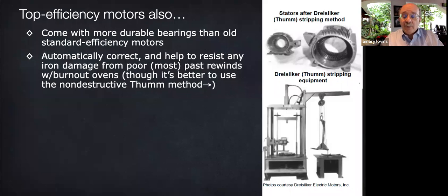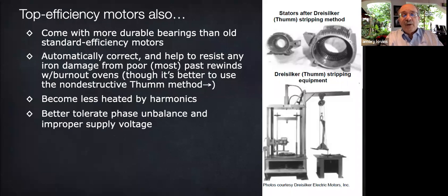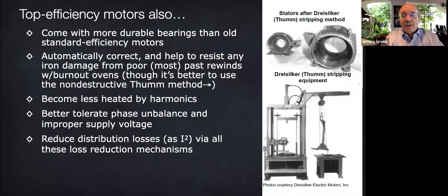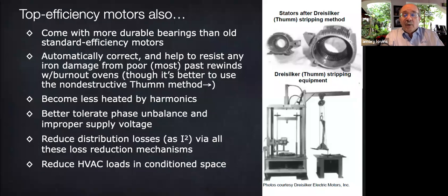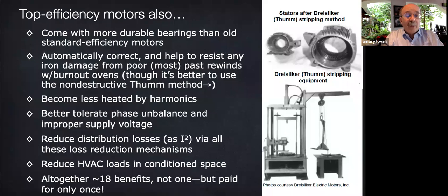Moreover, the top efficiency motors have less harmonic heating. They better handle phase unbalance and wrong supply voltages. They cut the I²R losses in the distribution wires and equipment. They need less cooling from cube law fans and pumps plus chillers if they're in conditioned space. So you buy the great new motor once and you get 18 benefits.